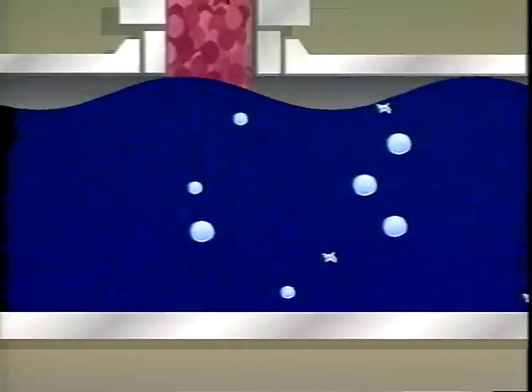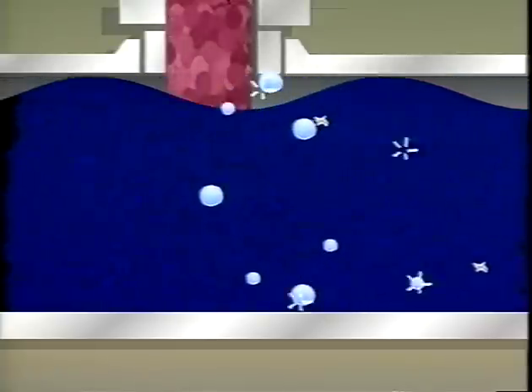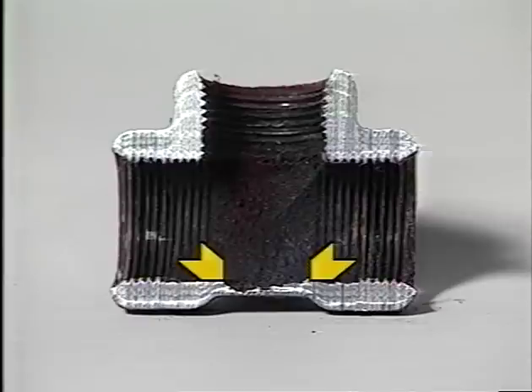The localized sudden reduction in pressure near the wall chips away piping and tube interiors. Oxide layers that otherwise would resist further corrosion are removed, resulting in accelerated deterioration of piping and equipment.